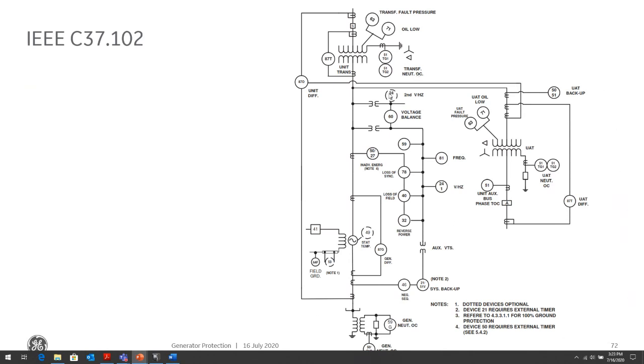A lot of them we've talked about, the 87. There might be distance, the 51V, to be able to back up for system faults. So coordinate for system faults, out-of-zone faults, or inadvertent energization, the loss of sync or out-of-step, or 78, loss of field protection, reverse power for loss of prime mover, our volts per hertz because for overfluxing, and our 59G and our 27 TN or 27 under voltage or third harmonic voltage differential.